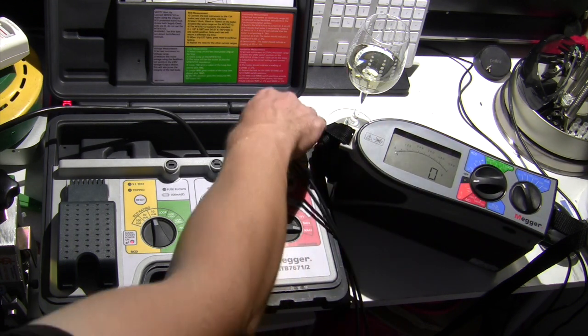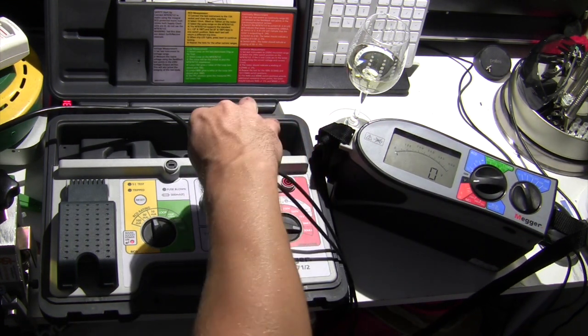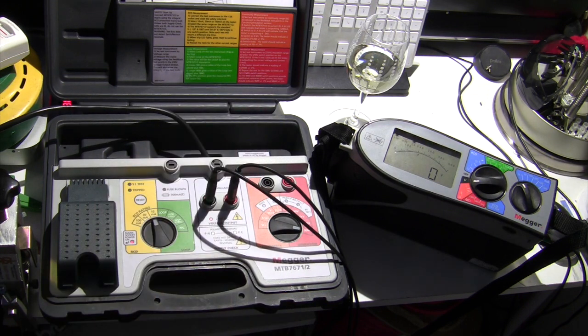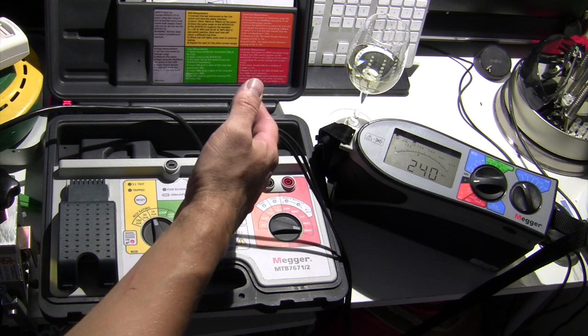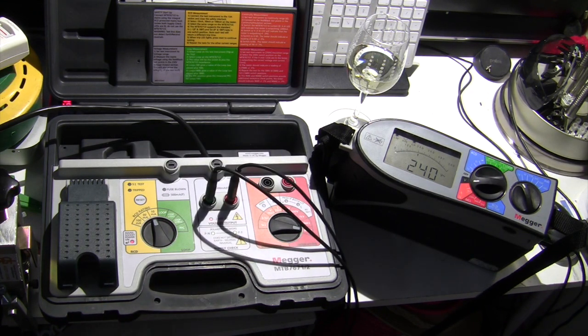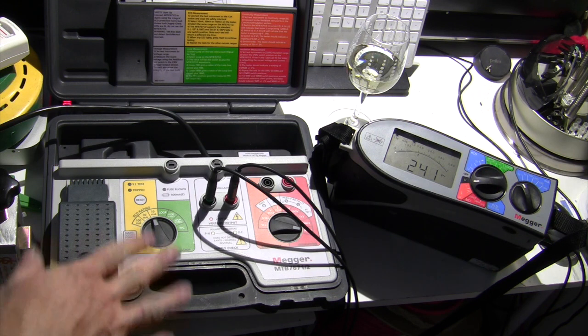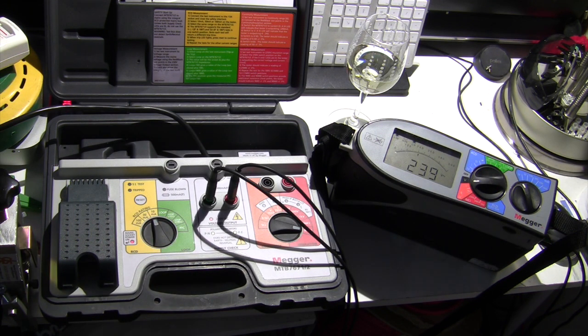And we're on the voltage setting, so we're just going to plug in the probes, and obviously, like I say, we should see somewhere around the 240 volts, because we're in the UK here. Now, the dead tests aren't going to make any use of the blue neutral probe. We've only got the brown live and the green earth probe in there. So in order to check that we haven't got any problems with our third lead, our neutral lead, it's best every now and again to rotate one of these cables with the neutral, just to make sure that it in itself is healthy and isn't wearing out, hasn't got any high resistance joints around the probe plug or anything like that. So we should get the same sort of readings regardless of which probe we use, but it's good to rotate them around a bit.